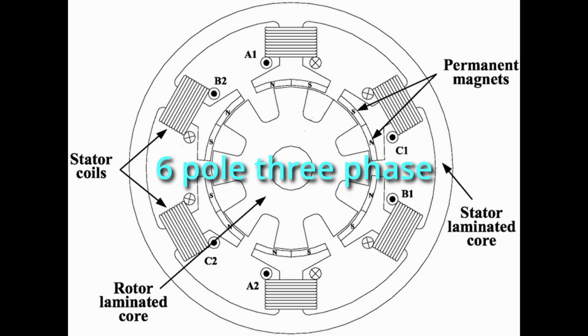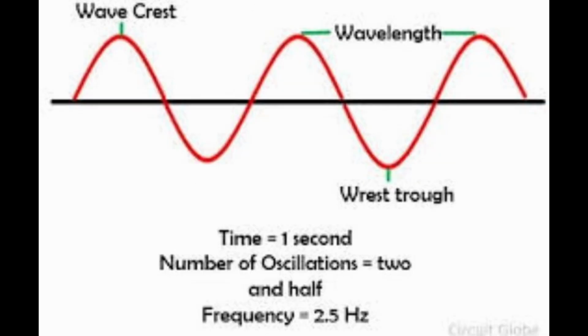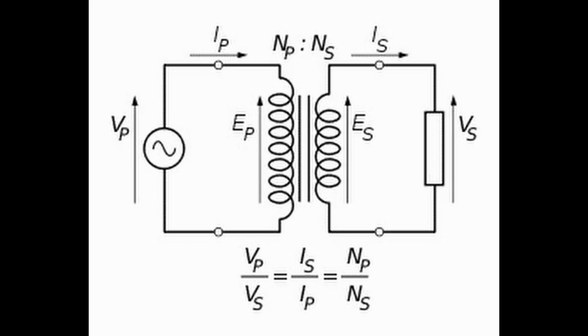The difference between a hydro turbine generator and those of other technologies is that the turbine rotates much more slowly, and if it is directly coupled, will not achieve close to 50 revolutions per second. This issue is overcome by having significantly more pairs of magnets than other turbines, so that 50 or 60 Hz can still be achieved. Electricity from the generator is stepped up, or has its voltage increased, using transformers, so that it can be exported to the grid to power our electrical needs.